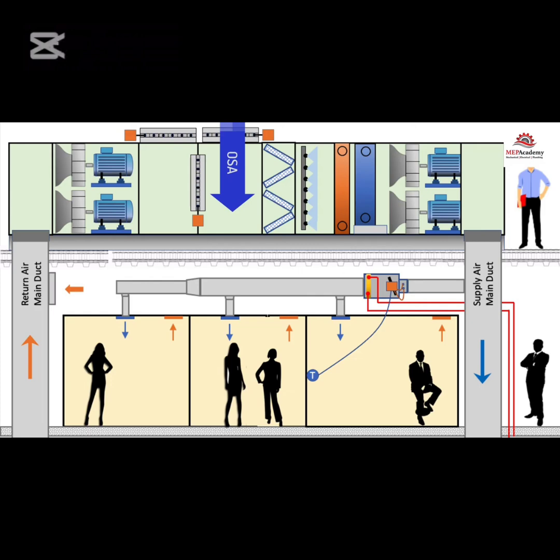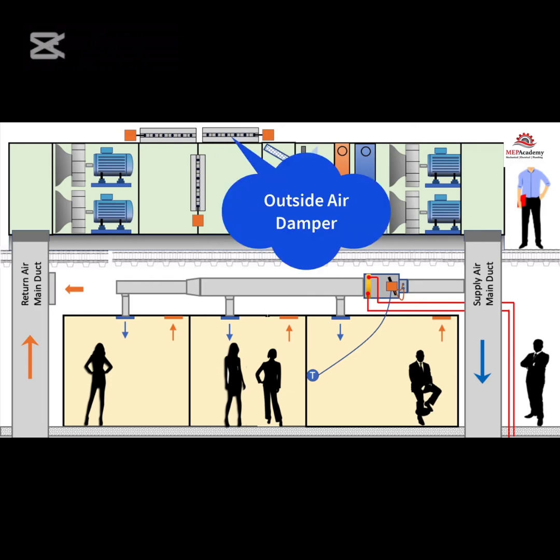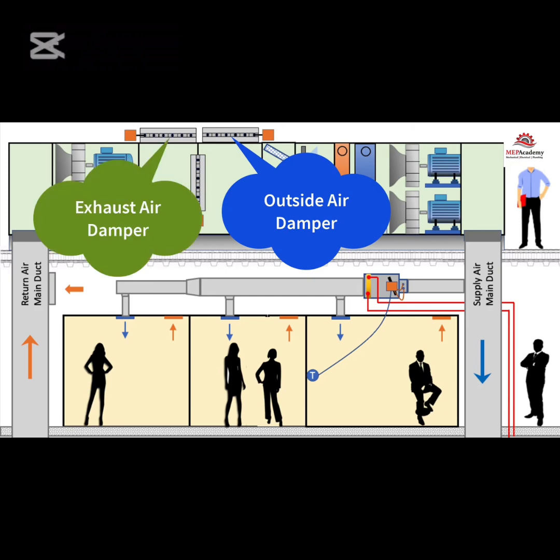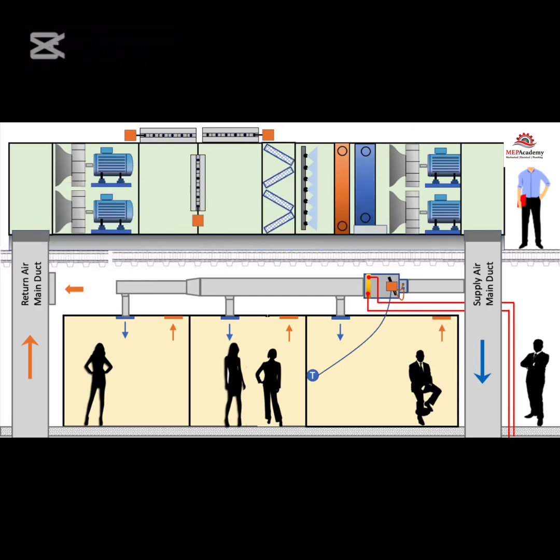code-mandated ventilation air. As the outside air damper opens to let more ventilation air in, the exhaust damper will open approximately the same amount to let air out. Economizers save energy by using the outside air to cool down the building when the temperature is lower than the return temperature or some set value.